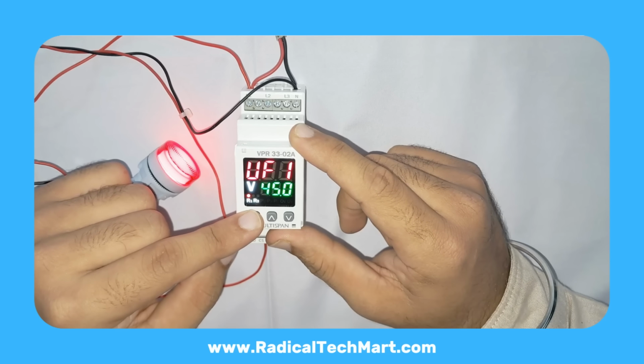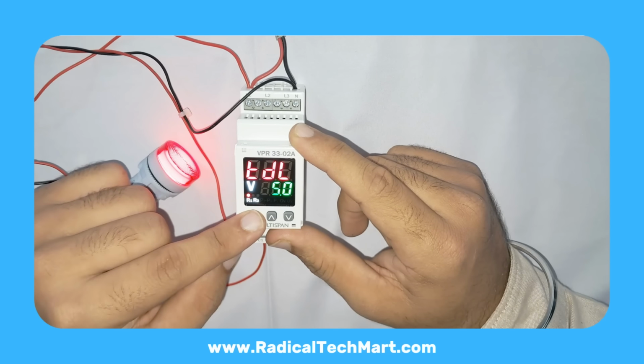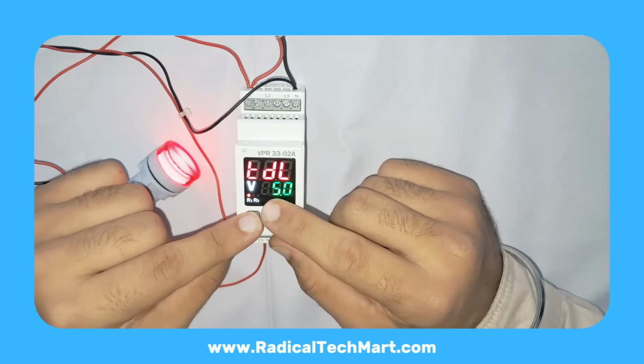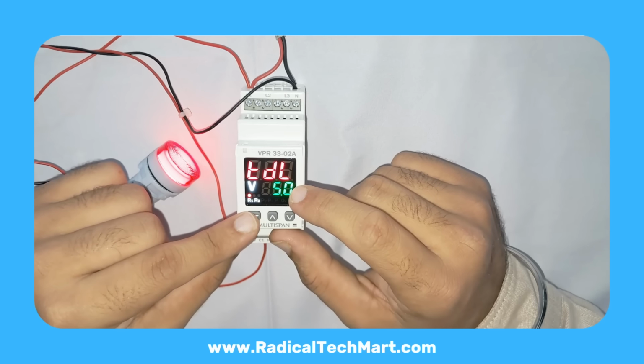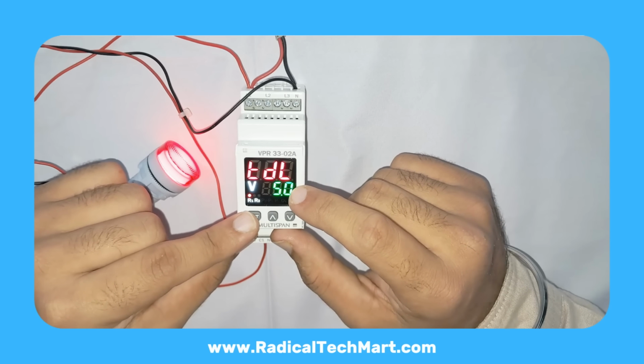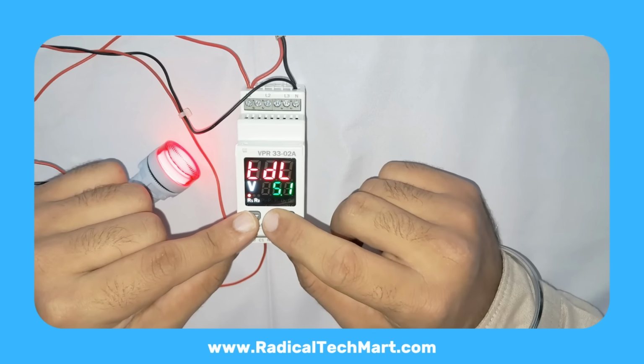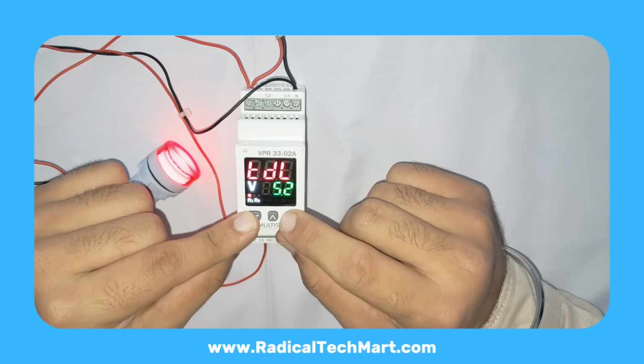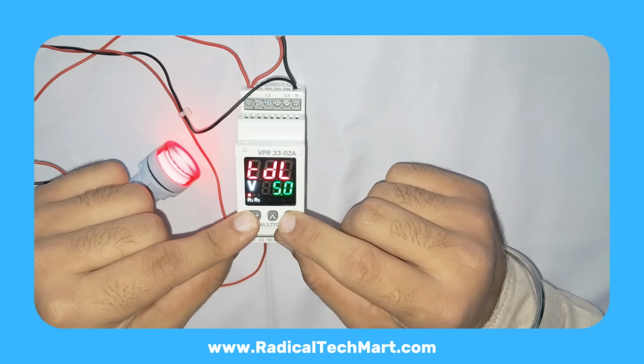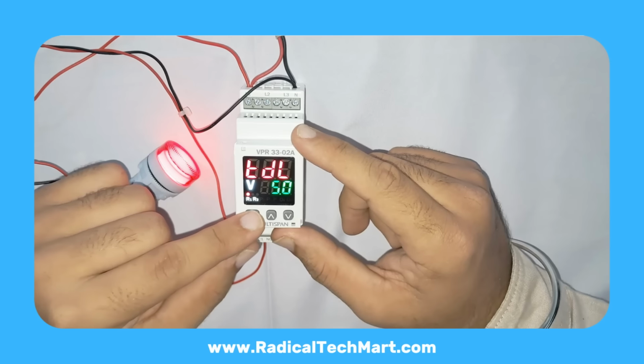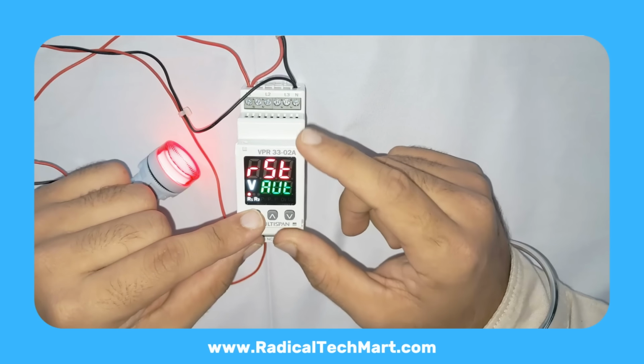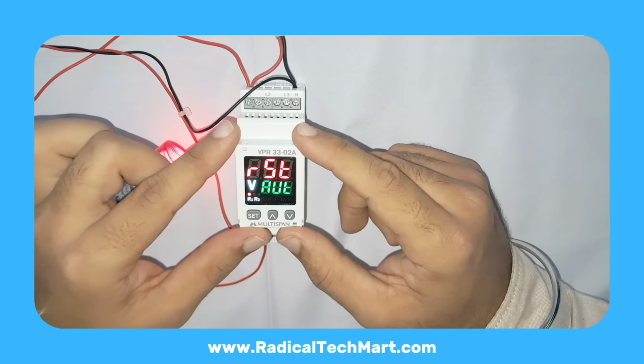Press Set to proceed. Trip delay time, TDL. The next parameter is TDL, trip delay. This is the time delay before tripping when a fault is detected. You can adjust the time in seconds, based on how fast or slow you want the relay to react. Press Set.